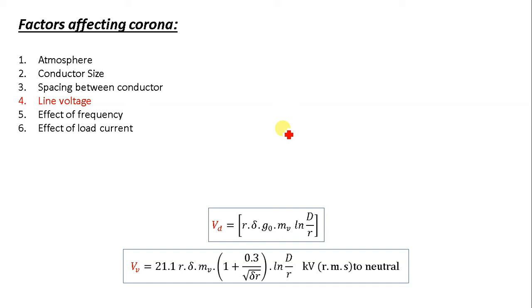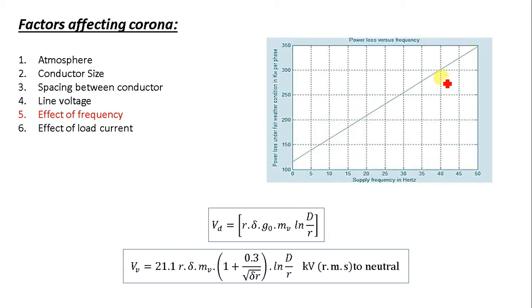The next factor is the effect of frequency. Corona loss is directly proportional to system frequency. When we derive Peek's formula and Peterson's formula to find corona loss, it will be shown that corona loss depends upon frequency. If system frequency increases, loss increases — that is why in an HVAC system corona loss is greater compared to an HVDC system.